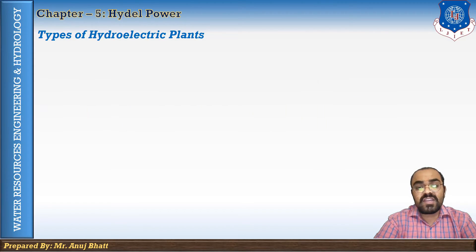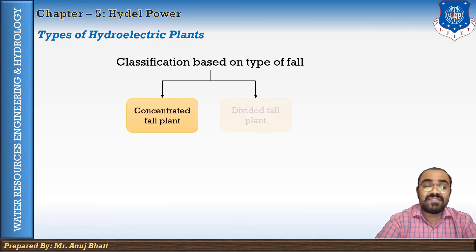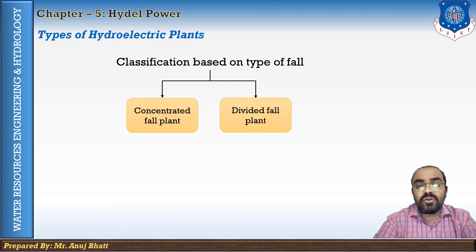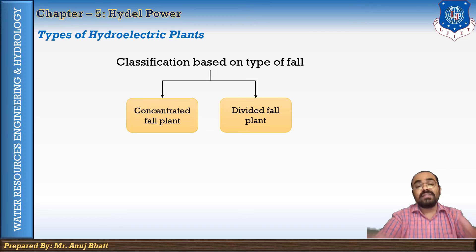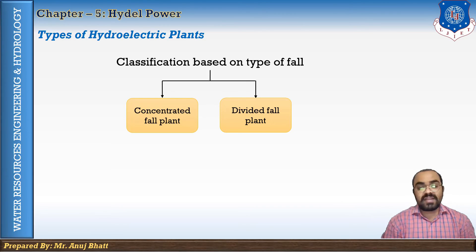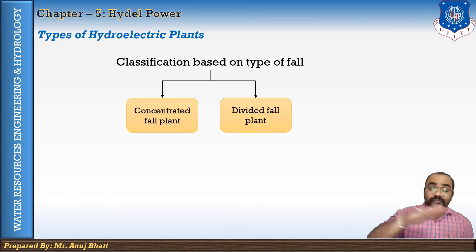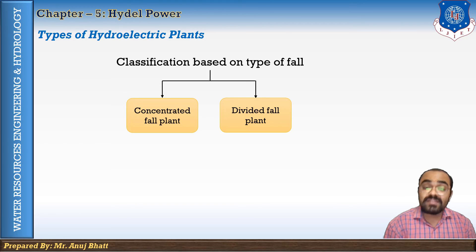The classification based on type of fall includes concentrated fall plants and divided fall plants. In concentrated fall plants, the powerhouse is located close to the dam or weir to utilize the entire created head as a concentrated fall. In divided fall plants, the powerhouse is located at a considerable distance downstream of the dam to utilize the steep fall in the ground surface, increasing the operating head. Divided fall plants are generally more expensive than concentrated head plants.